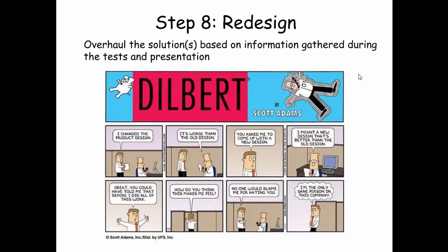So let's say you had this insulin pump, somebody wears it while playing soccer, and it gets dropped, and it breaks very easily. So that's something that you're going to consider in this redesign. Or people are saying, you know what, I'm running out of insulin before I should. So you need to make the place where the insulin goes bigger so it can hold more insulin. So that's when you would find this out, and that would be part of this redesign.